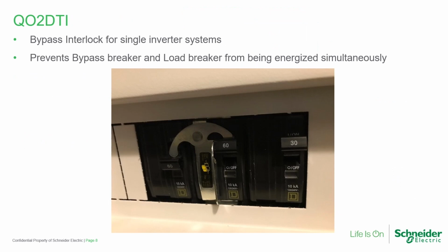A single inverter system will have a bypass interlock T-bar that ships with the PDP and with the mini PDP. You can see the Square D part number up top there, QO2DTI. This interlock prevents the bypass breaker and the load breaker from being energized at the same time.